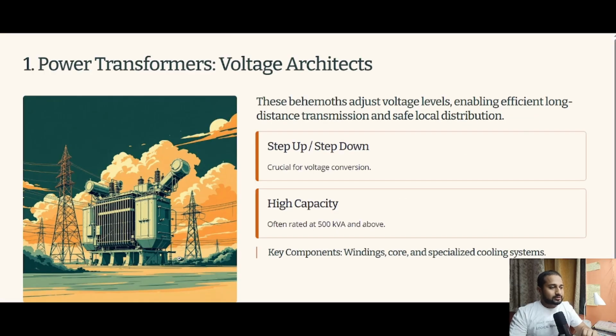So first equipment, that is power transformer. Power transformers are also known as voltage architects. These are very big in size and they adjust the voltage level, enabling efficient long distance transmission and safe local distribution of the energy. They also step up and step down the voltage, and they are crucial for voltage conversion. They have high capacity. Often the high capacity starts from 500 kVA and above.